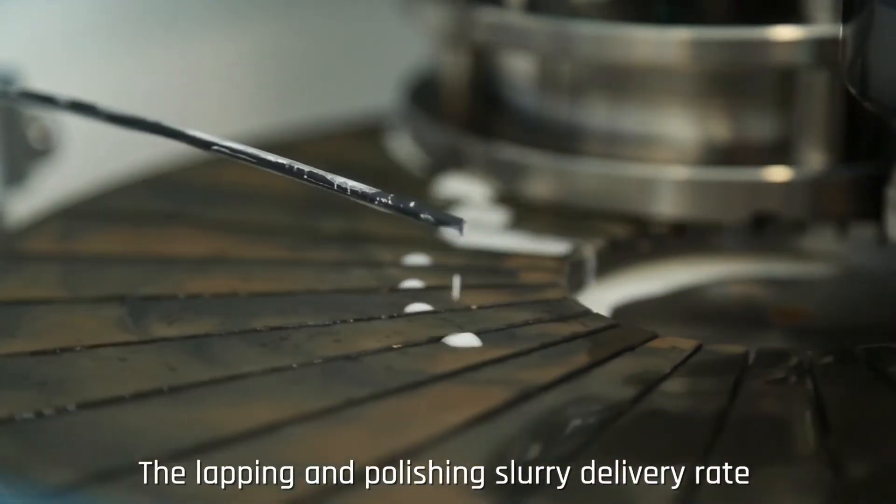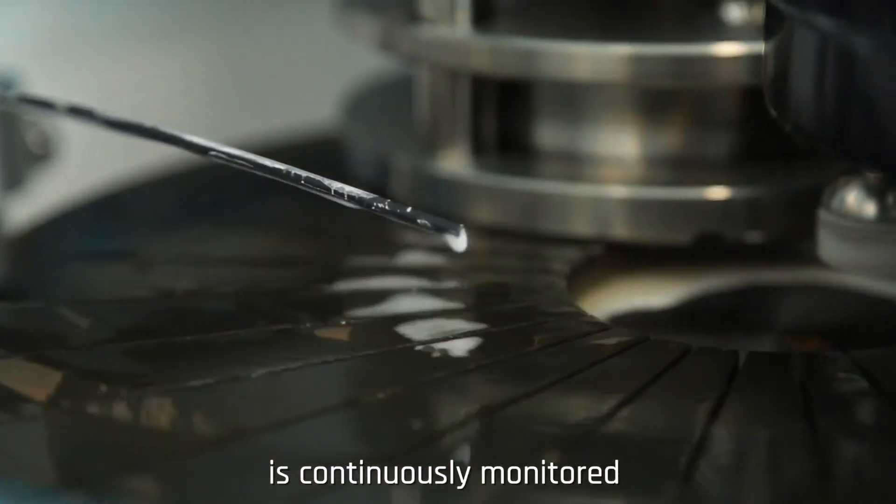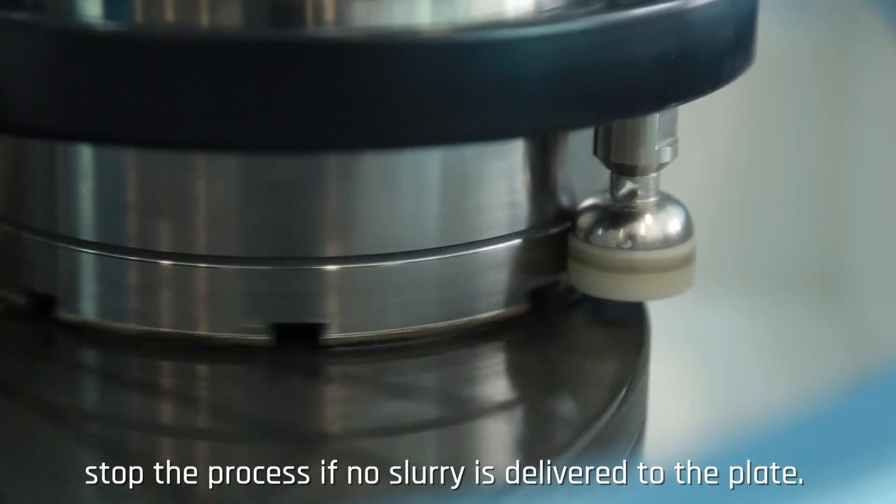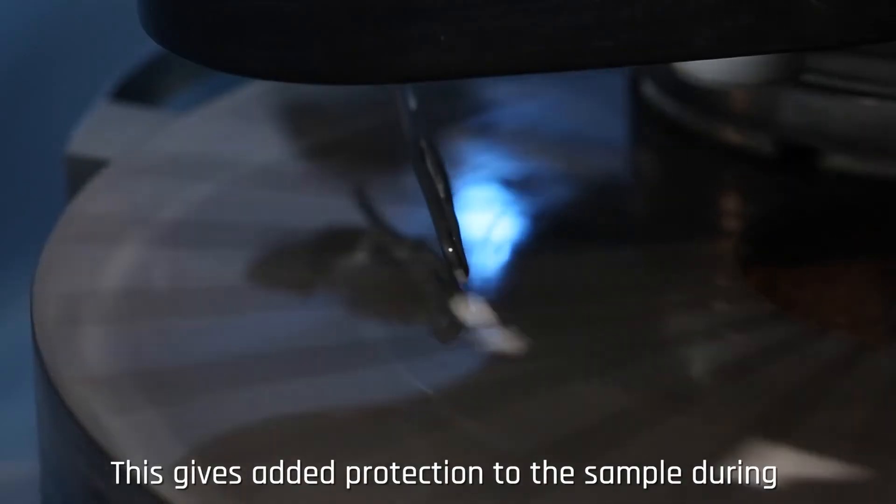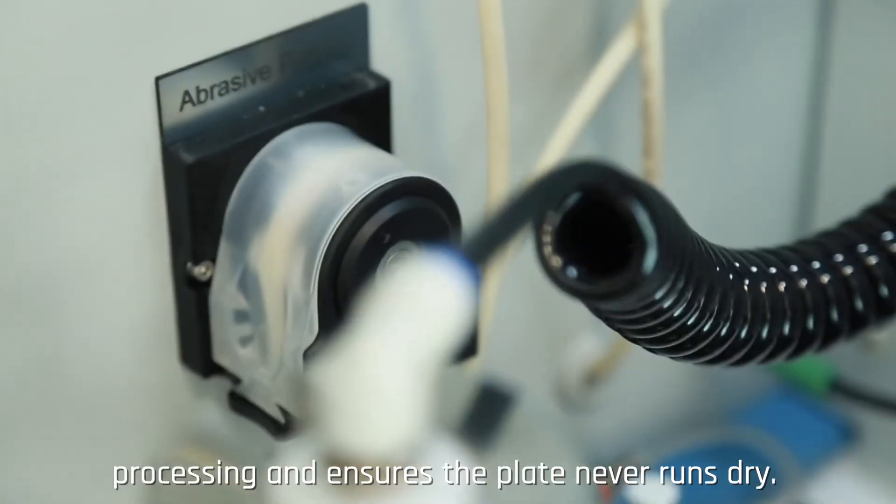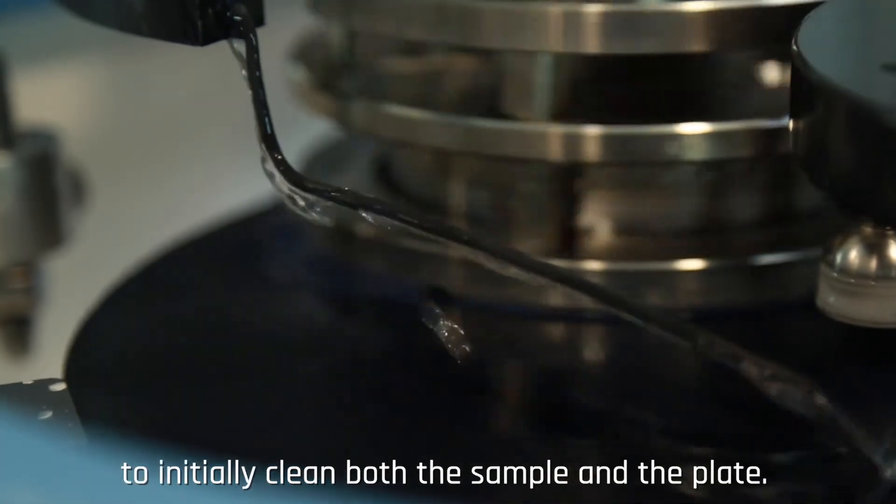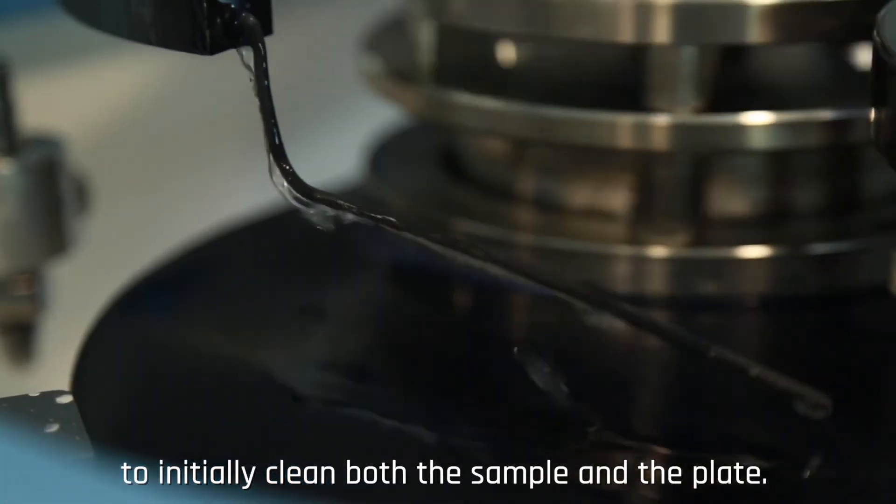The lapping and polishing slurry delivery rate is continuously monitored using an infrared sensor which will automatically stop the process if no slurry is delivered to the plate. This gives added protection to the sample during processing and ensures the plate never runs dry. At the end of the polishing process the plate can be flushed with deionized water to initially clean both the sample and the plate.